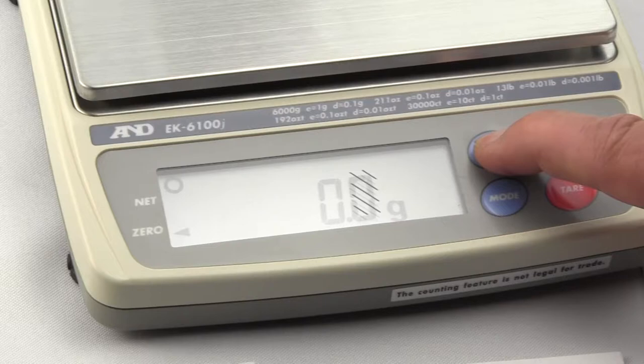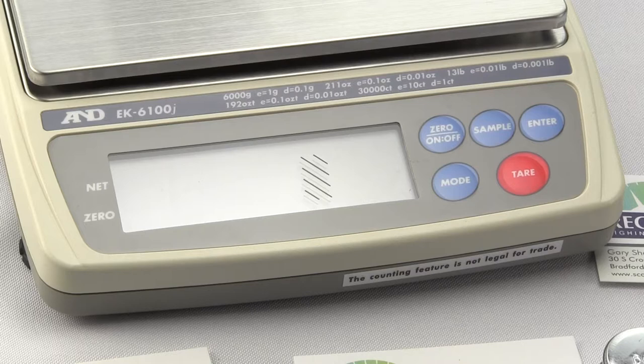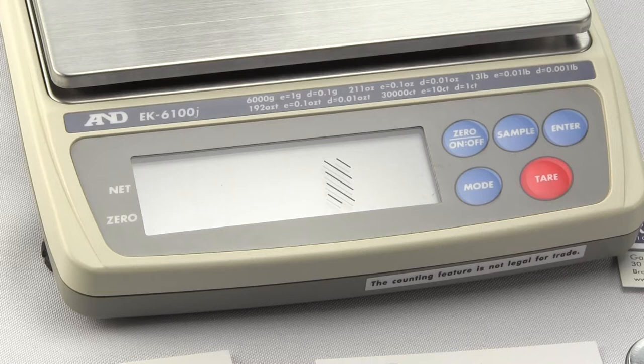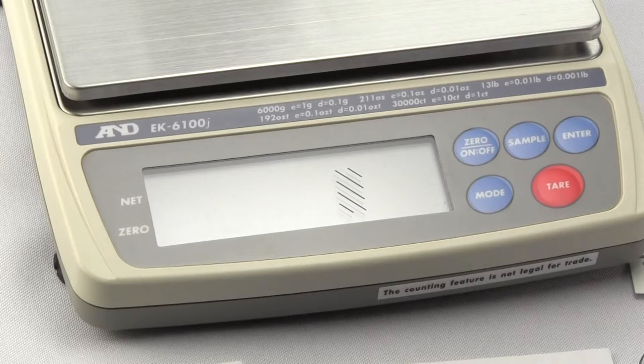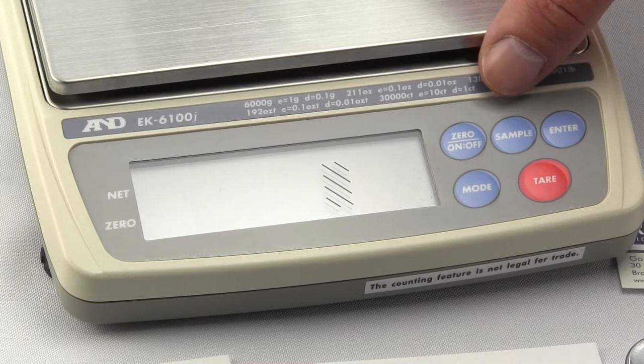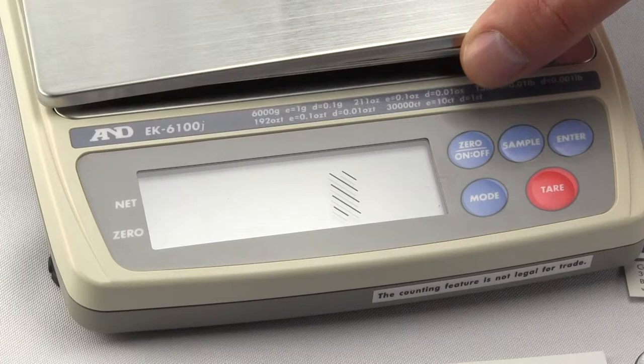So I'm going to shut off the scale so you can actually see. So those lines stay right on the scale. This is because again D is the minimum division that the scale can display and E is the verified scale division or value of the verification scale division for legal for trade. You'll also notice here the weighing platform. You have a nice large removable weighing platform. It measures 5.2 inches by 6.7 inches.